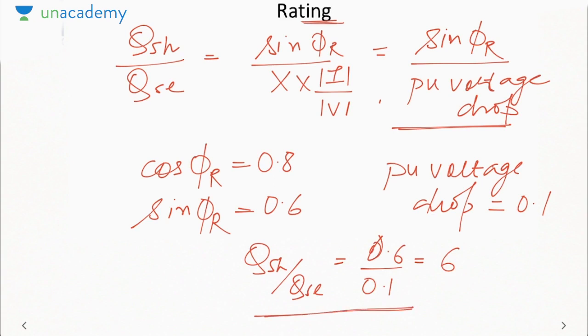That means for the same voltage improvement, the rating of shunt capacitor required will be more than the rating of series capacitor. And since the rating has increased, the cost of the capacitor required will also increase. If the cost increases, that means shunt capacitor will be more costly. But with series capacitor, since the fault current increases, we have to increase the protection system. That will also increase the cost, which is being compensated here. So we cannot say that shunt compensation will be more costly. Instead, series will be more costly due to the increase in cost of the protection system required.